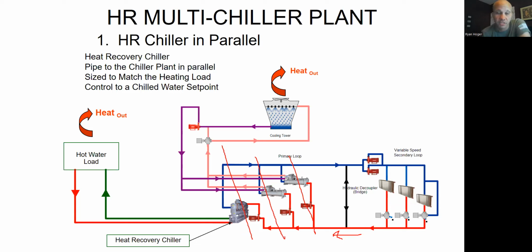So I added this heat reclaim chiller in parallel with the regular chiller plant, which could be 1, 2, 3, 4, 5 chillers. So he's in parallel. This guy is going to be piped to the chiller plant that way. He's going to be sized for the heating load. What does that mean? You're going to get a chiller and you're going to size it for heating, right?